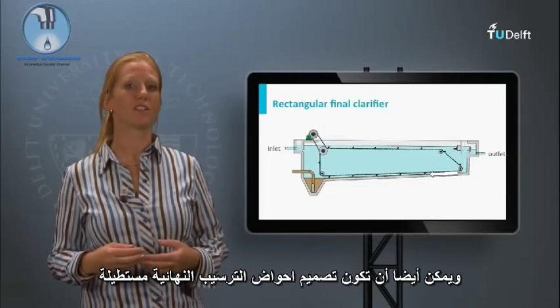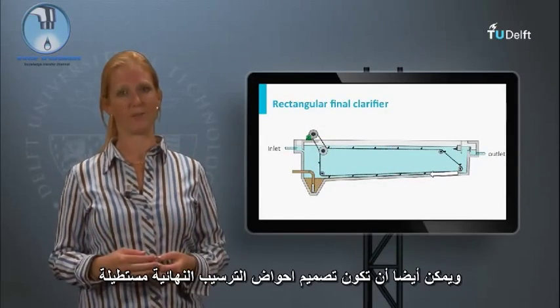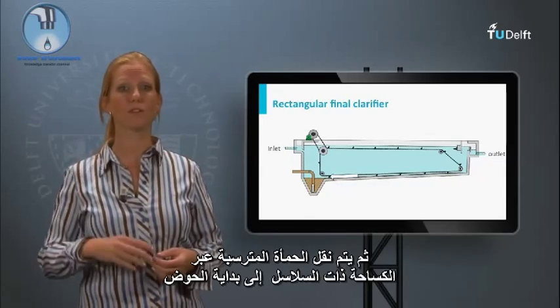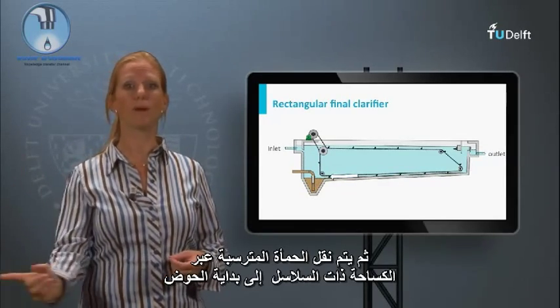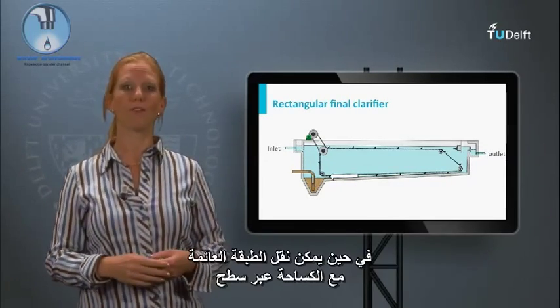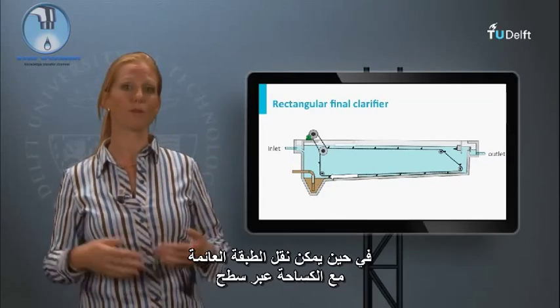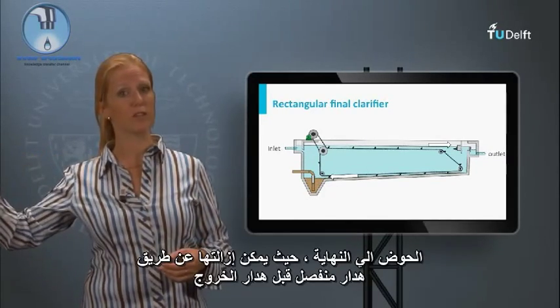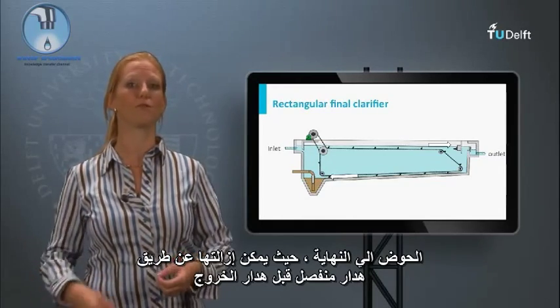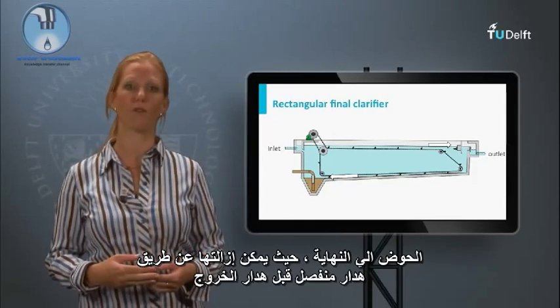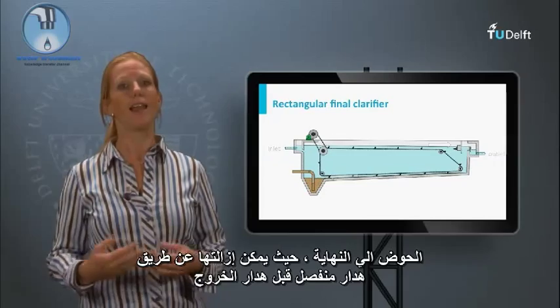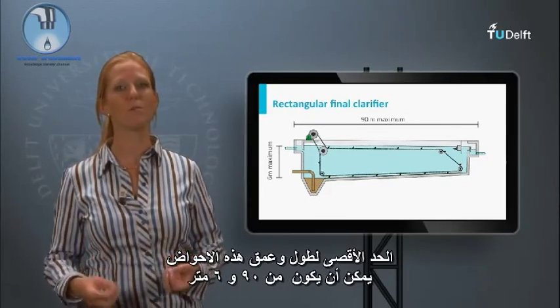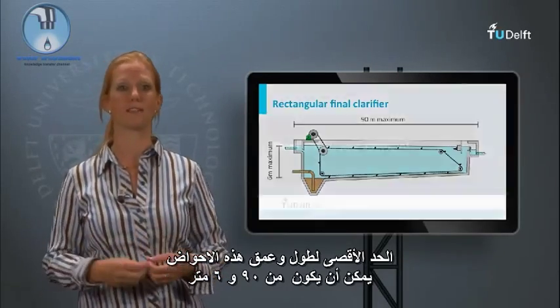Final clarifiers can also be rectangular in design. The settled sludge is then transported via chained beams to the beginning of the tank, while the floating layer can be transported with the beams passing the surface of the tank to the end, where it can be removed via a separate weir before the overflow weir. The length and depth of these tanks have a maximum of 90 and 6 meters.